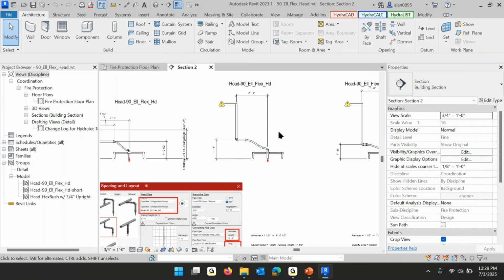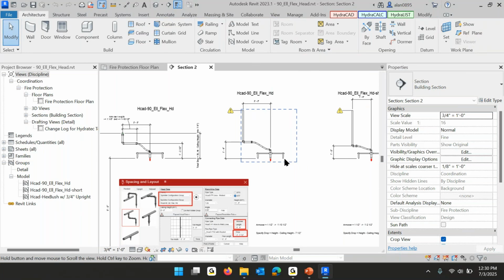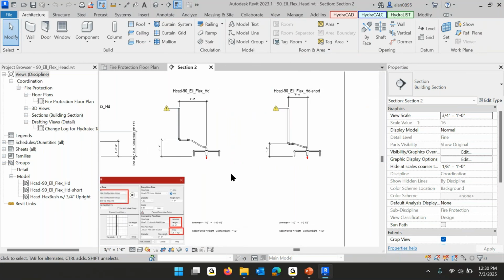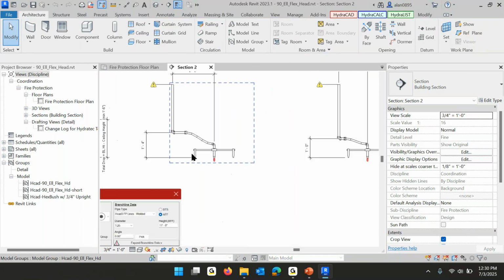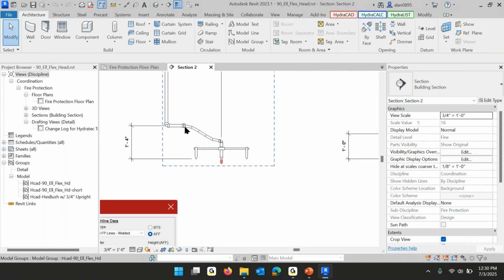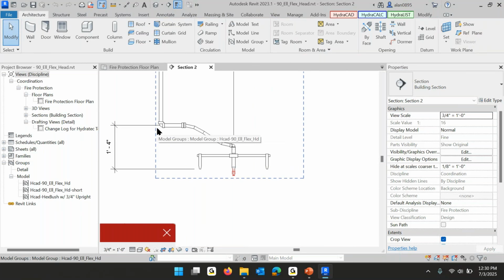Yeah, exactly. I guess more specifically, I think you kind of touched on it when you were talking a little earlier. What I was looking for is right now, even in the connections you're showing here, it shows the flex go to like a 1-inch coupling and then like a nipple going into the elbow. What I was seeking to say is, hey, can we get the flex to just go straight into that 1-inch elbow and always kind of ignore that arm over? Yes.